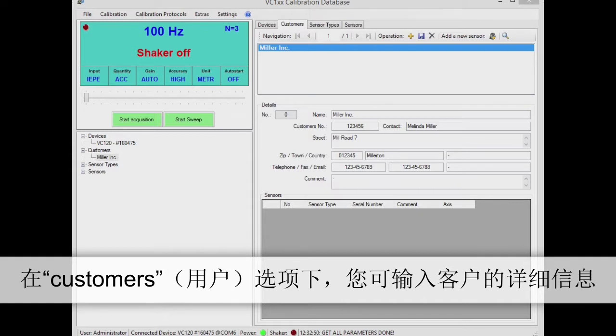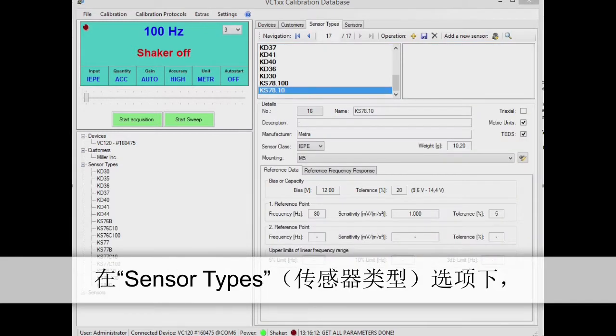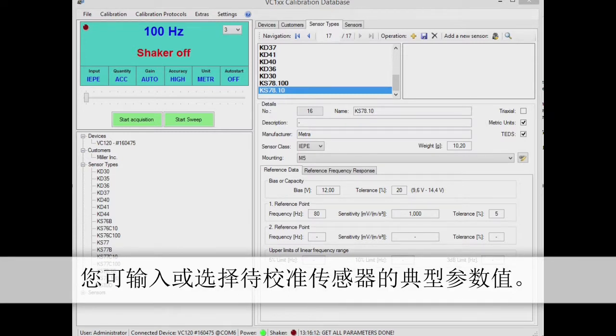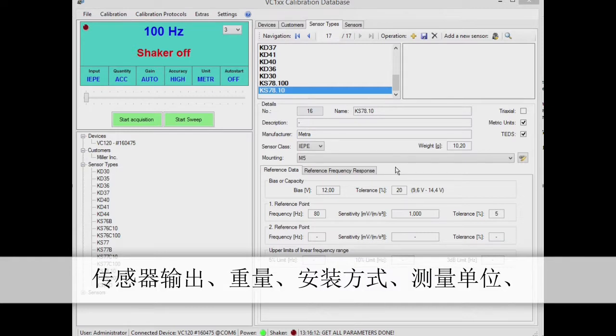Under customers, you can enter the contact details of the client commissioning the calibration. Sensor types is used for entering and selecting typical parameters of the sensor to be calibrated. Here you can specify the type description, the manufacturer, sensor output type, weight and mounting method.